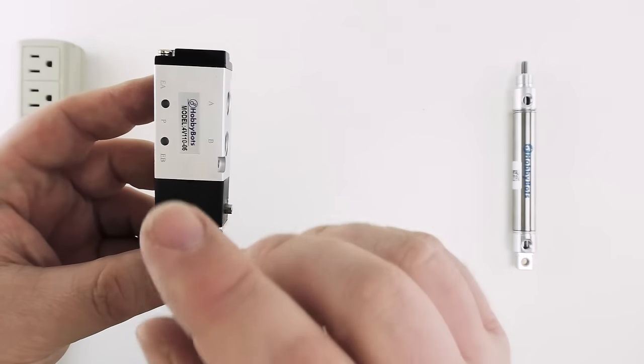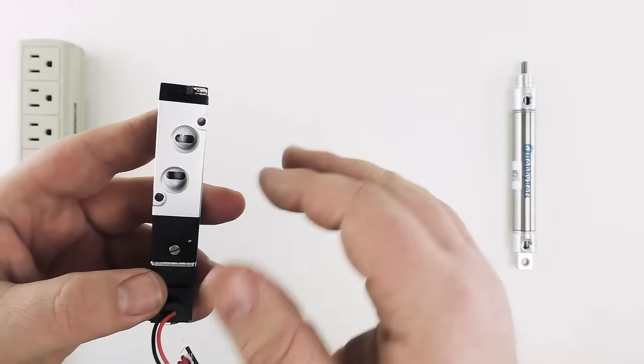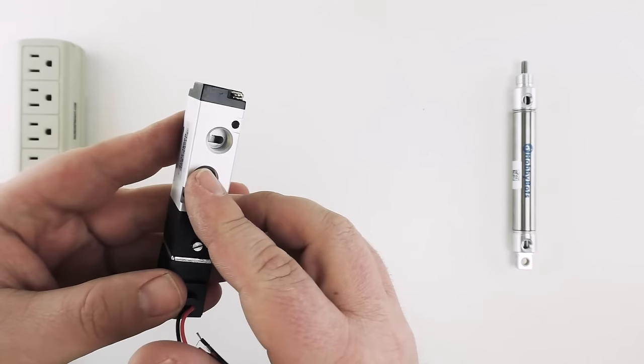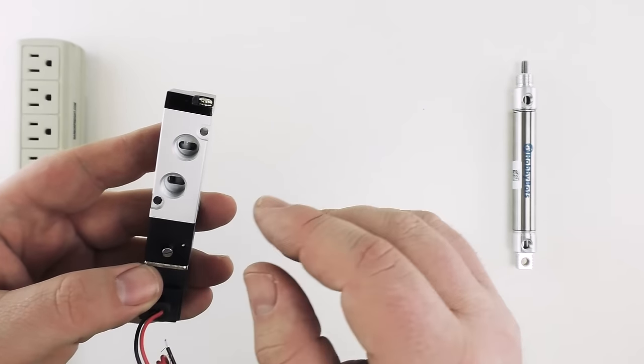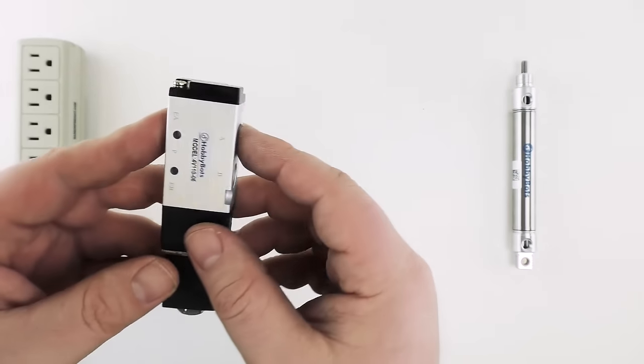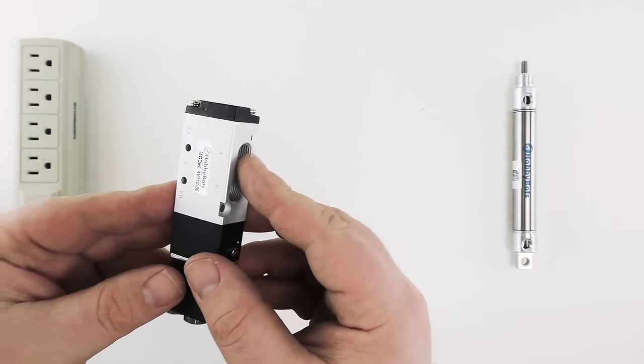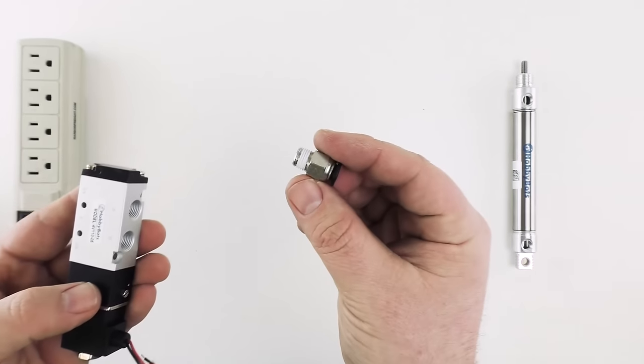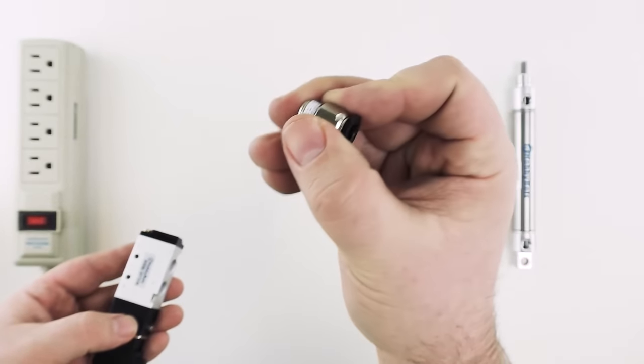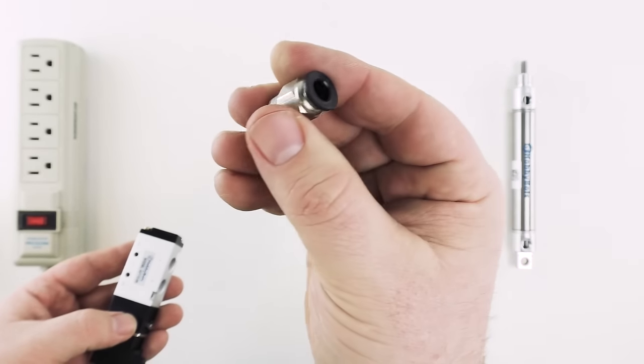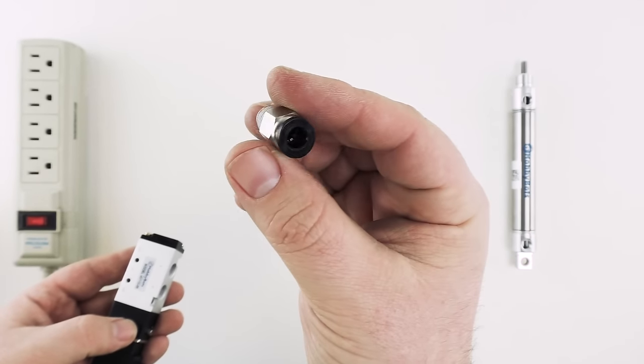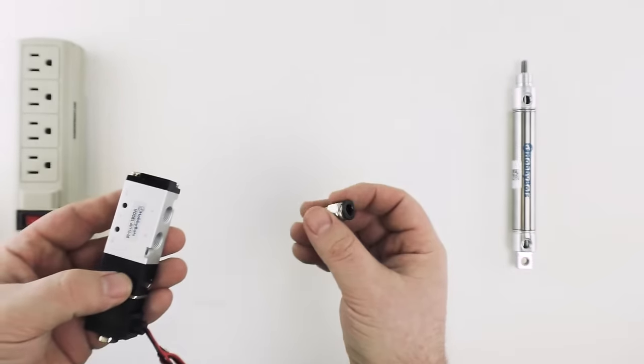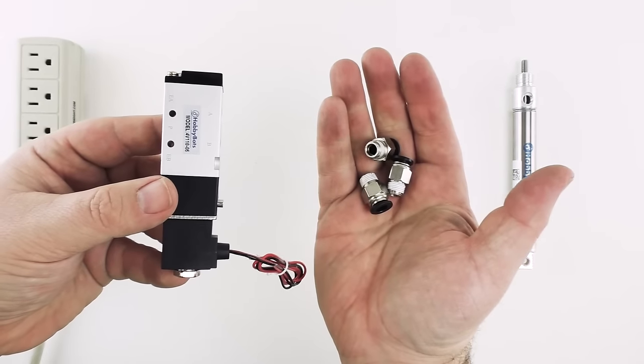So the first thing we're going to do is install fittings in our solenoid. Now solenoids come in a variety of sizes. This one is an eighth inch NPT solenoid. That means that these female threaded holes are one eighth inch NPT. We have several fittings the correct size to match. You'll see that these fittings are threaded on one end and the other end has a plastic ring to accept a quarter inch outer diameter air line.